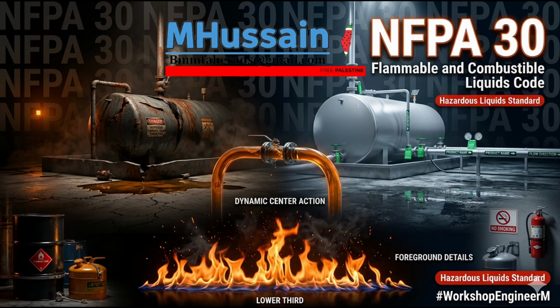The weld connecting the roof to the vertical side shell is intentionally calculated to be structurally weaker than the massive welds connecting the side shell to the heavy bottom plate resting on the foundation. Because if the internal pressure outpaces the venting and the tank is inevitably going to fail, you absolutely dictate where it fails. Exactly. If the bottom seam failed, the pressure would lift the entire cylindrical shell off its foundation, releasing a 50,000-gallon tidal wave of burning fuel that would obliterate the dikes and sweep across the facility.